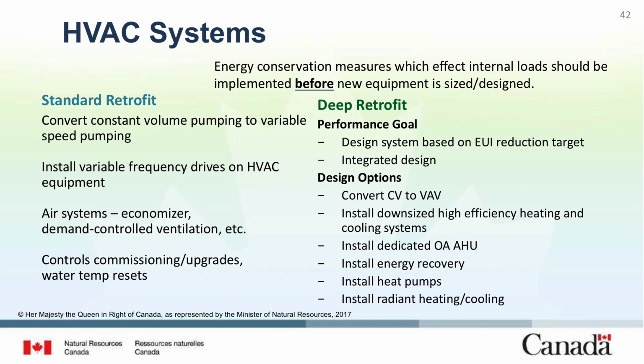If you put energy recovery on outside air ventilation, you can reduce your ventilation loads by 50%. Installing heat pumps is a huge way to reduce energy usage. Then there's radiant heating and cooling that allows you to provide heating and cooling to the facility with much lower energy use than standard forced air systems. To be innovative, you can apply a combination of these strategies into a deep retrofit.